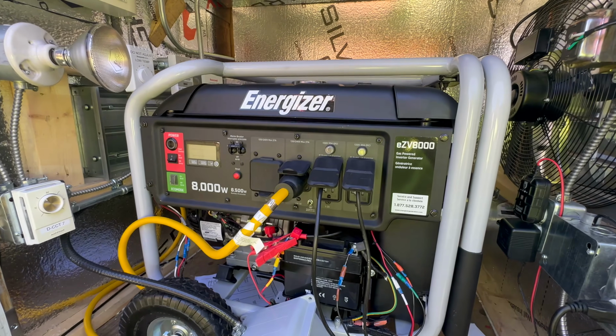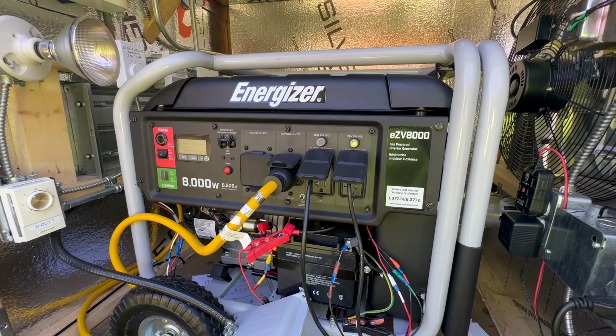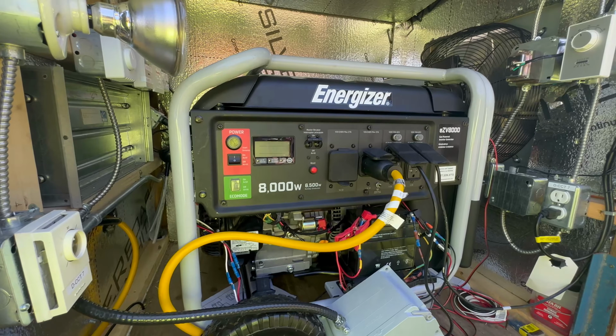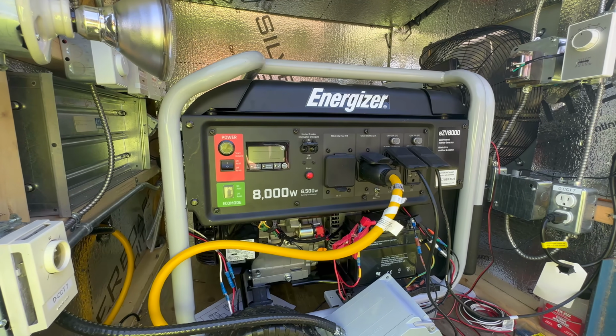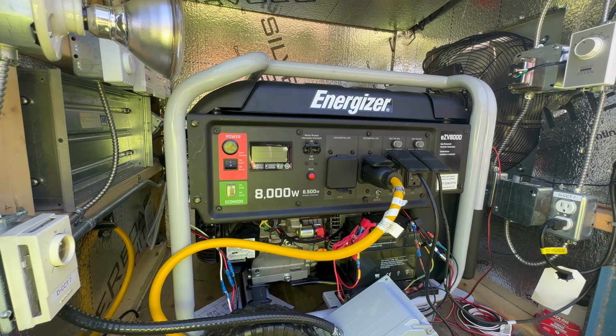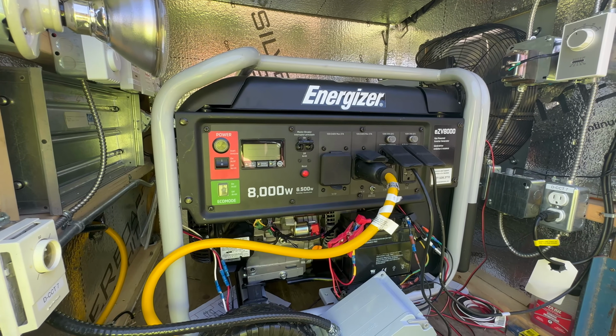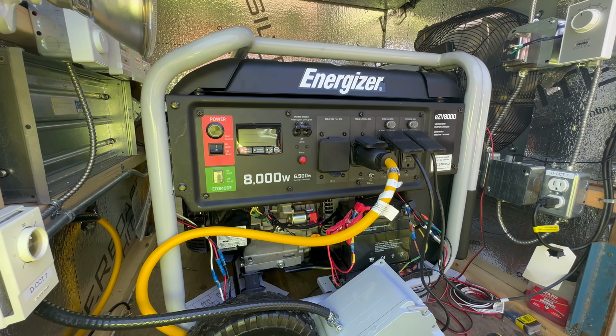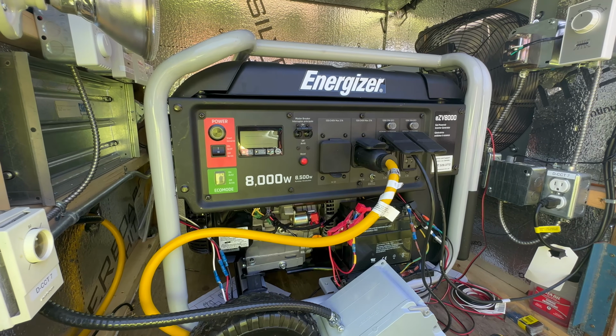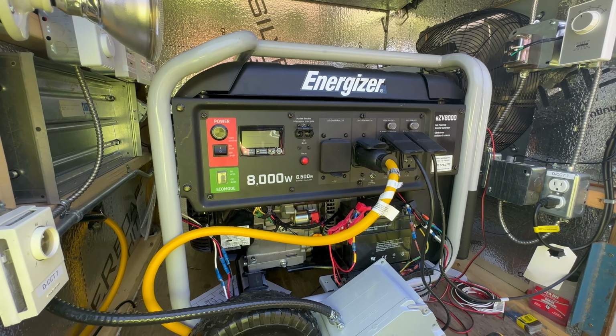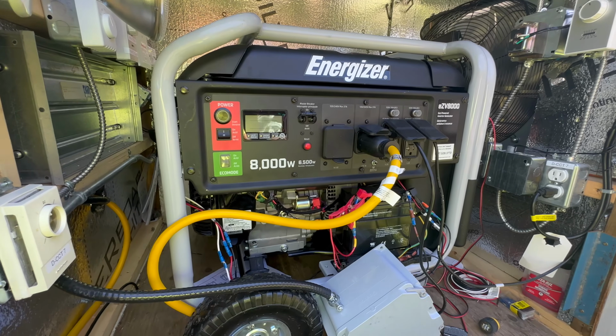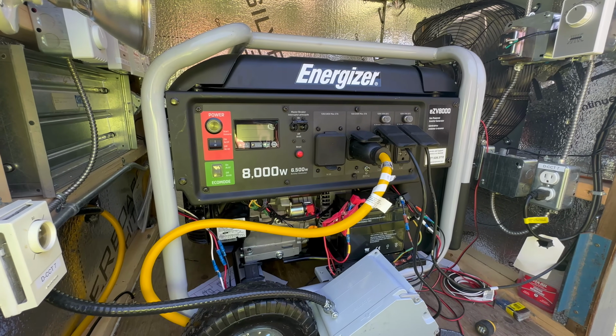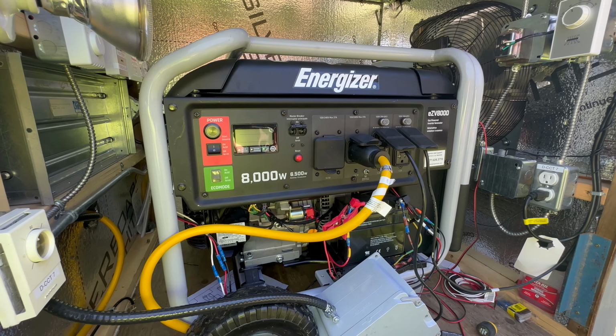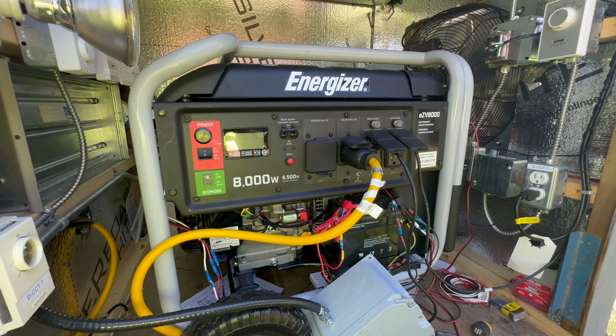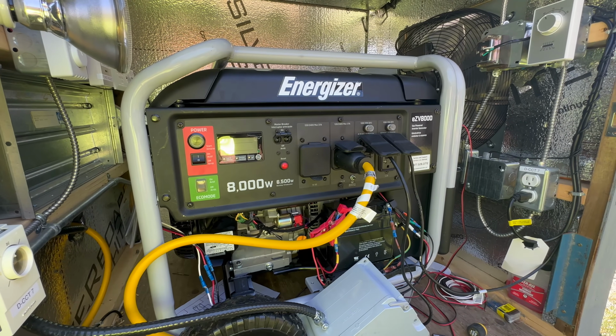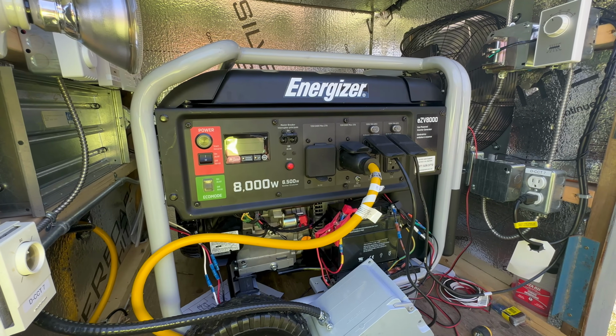The reason I went with an inverter generator instead of a regular generator is generators that use inverter technology put out much cleaner power and a nicer AC sine wave. The reason that's important is a dirty sine wave can be damaging to sensitive electronic equipment, and that is measured in THD, or total harmonic distortion, which BC Hydro has their own set parameters of maximum allowable total harmonic distortion.